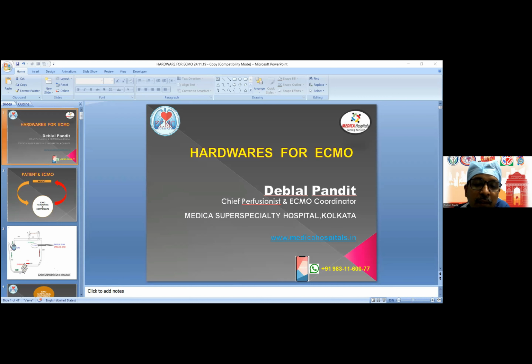This is a simple, disposable pump. If we think in detail, it has only 32 ml priming volume. And if we go back to our physics class of 10th, 11th, 12th, the working principle is centrifugal force, mv square by r. If there is no mass, this machine cannot start working.